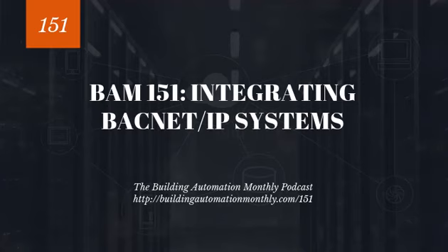So it's really important for us to understand that, because if we try to go and grab analog inputs or binary inputs, and we try to command those, which I see a lot of folks do, we will not be able to do that because they have no priority array and they don't support those services. They support the read property services, but not the write property services in most cases. Now, as I mentioned, we have to make sure our network is set up, and that is the next step.